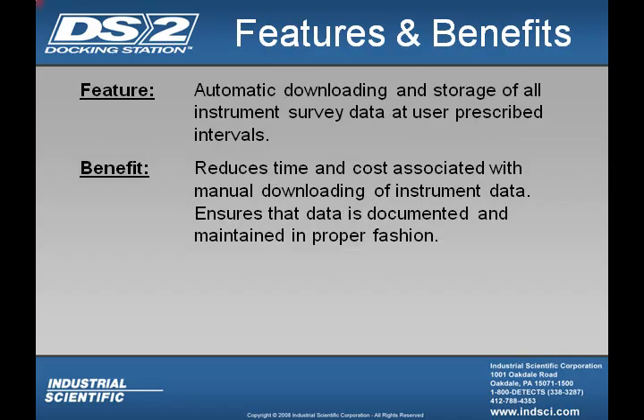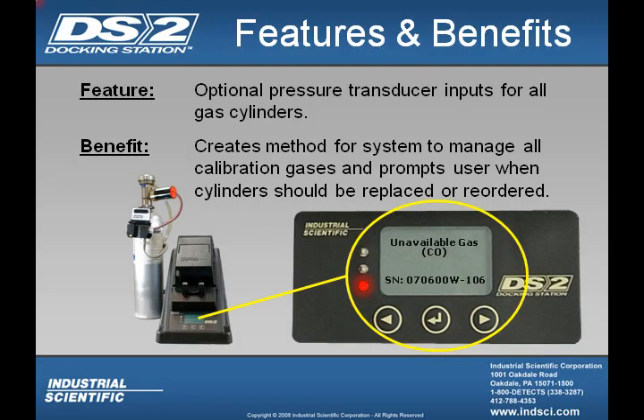You also have automatic downloading and storage of all instrument survey data at user-prescribed intervals. And what this will do is help reduce the time and cost associated with manual downloading of instrument data. And this also ensures that the data is documented and maintained in a proper fashion. Another feature of your docking station is the optional pressure transducer input for all your gas cylinders. And what this will do is create a method for our system to manage all calibration gases and prompt the user when the cylinders should be replaced.